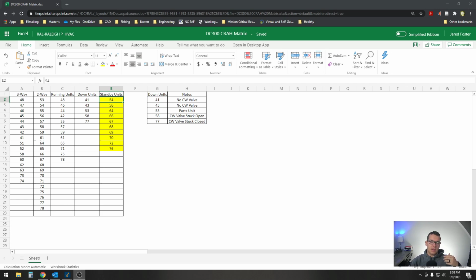At some point in the project, we had to valve off a bunch of the units under the floor because they have what's called a three-way valve. Those units are identified here. A three-way valve for the type of system we have is terrible, it just doesn't work, it's terribly inefficient. The performance and efficiency of the chiller system go way down when those valves are open, so we had to shut them and keep them shut.